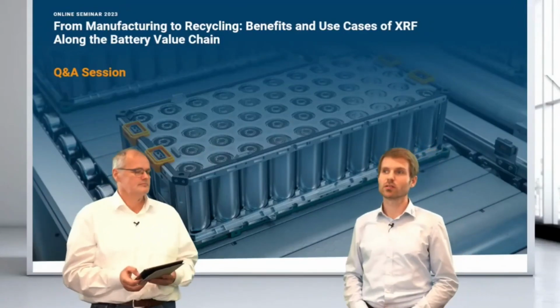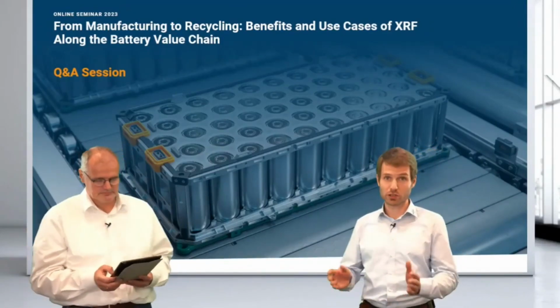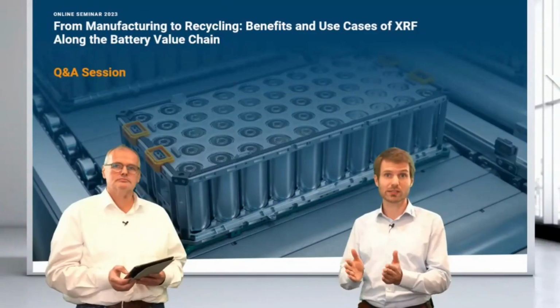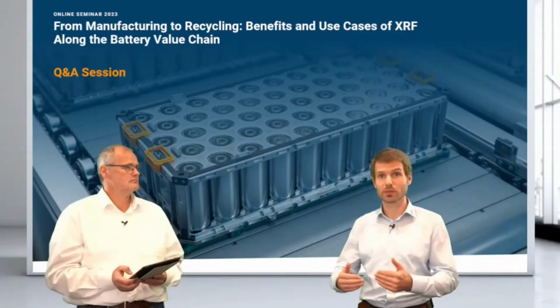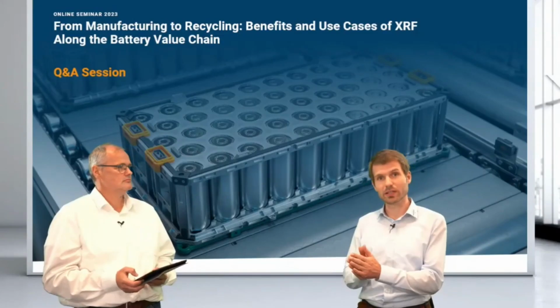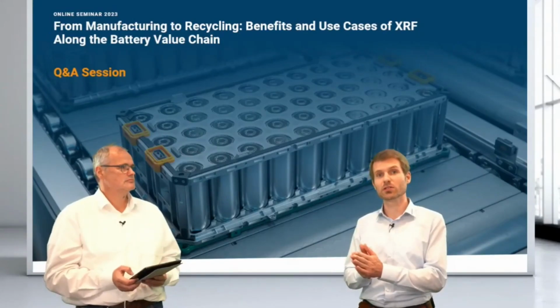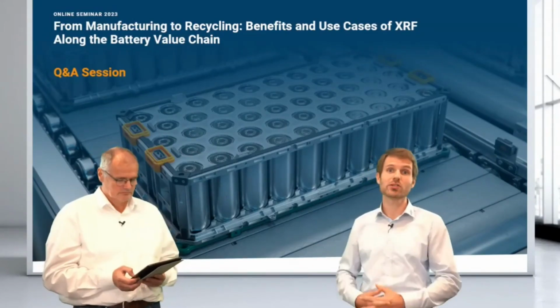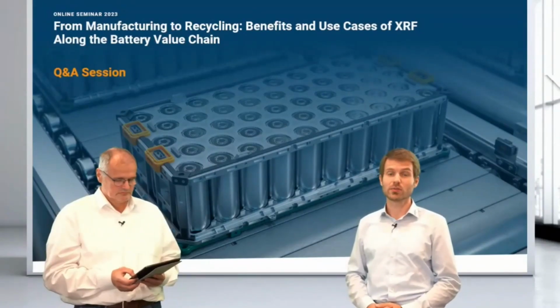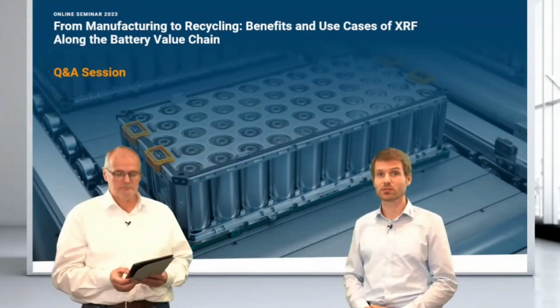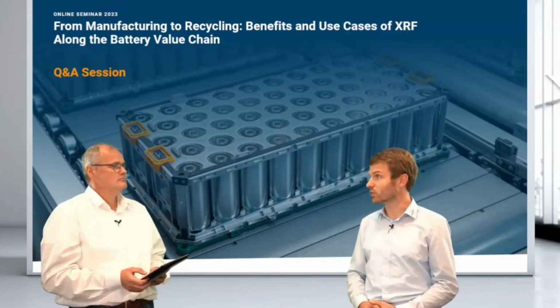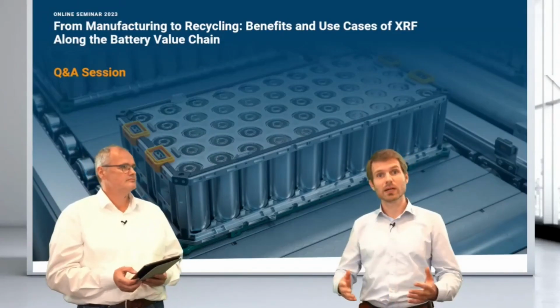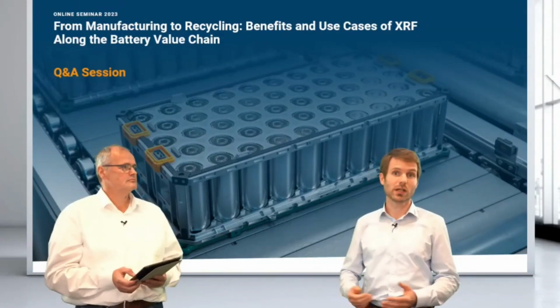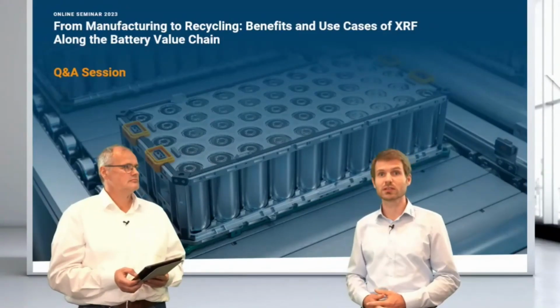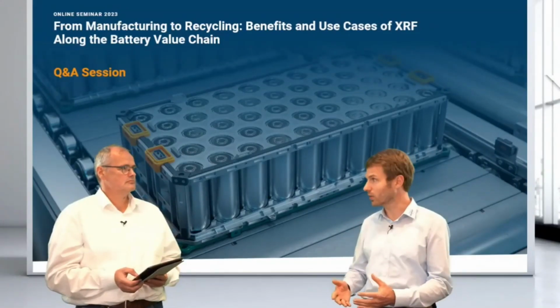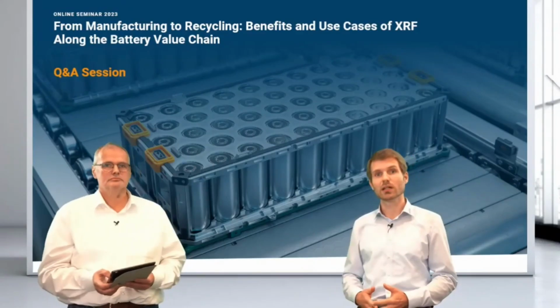Yeah. So fluorine has a very shallow penetration depth with X-rays. So we get only information from the very, very near surface of the material. However, we can still measure it relatively precisely, even to lower concentrations with especially wavelength dispersive systems. But that would mean that you have to press the sample. So you cannot use it in a liquid cup with a powder or a slurry. You would have to press.